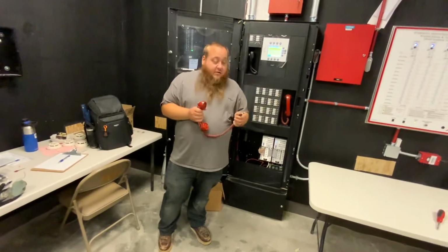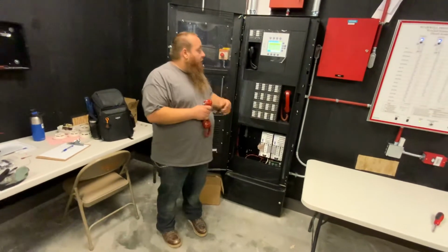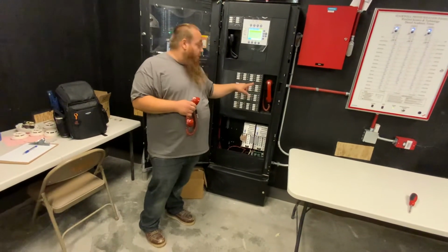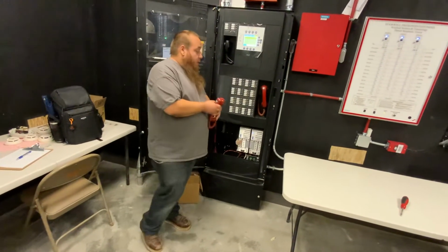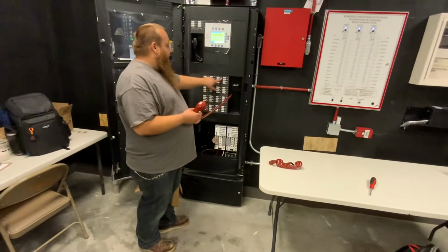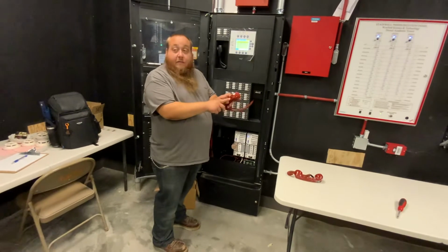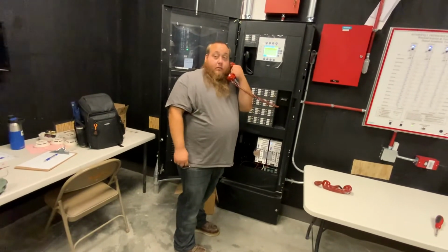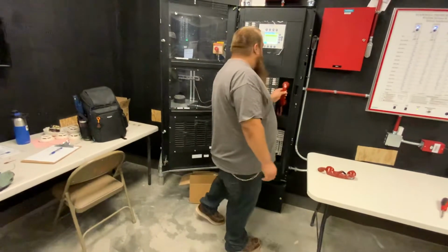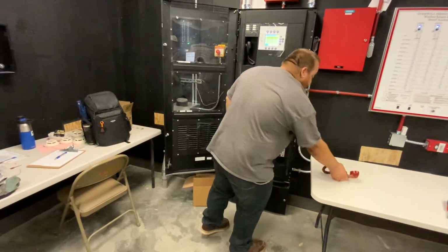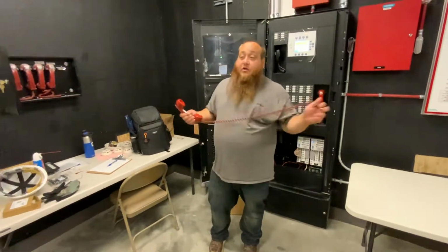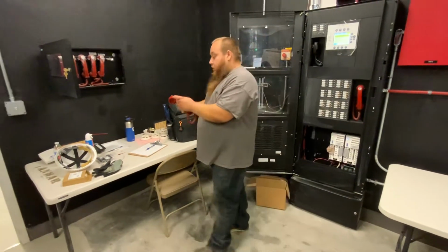So when you find those jacks, simply plug it in. It'll come up here, start beeping, and then your stairwell or your elevator lobby phone will start lighting up. And it's simple. You pick your phone up, you select the phone it's coming from, you hit your black button here, and you're able to talk to them. You have clear communication between those two spots. They come in handy because if you don't have many people on site, you can send a guy to investigate and one here to make sure the panel is still in normal condition.